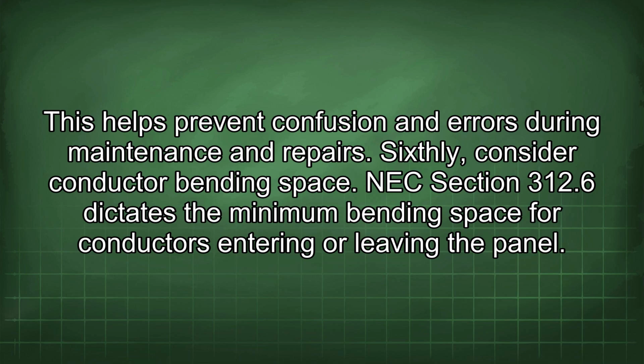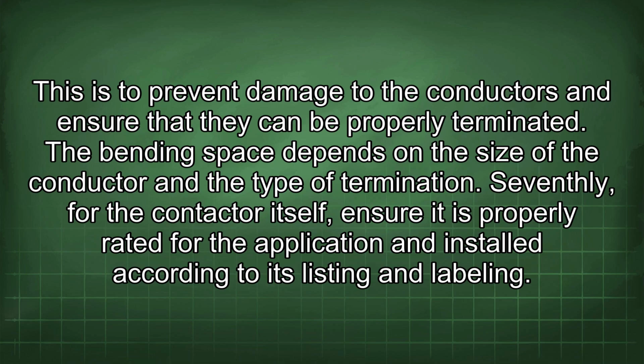Sixthly, consider conductor bending space. NEC Section 312.6 dictates the minimum bending space for conductors entering or leaving the panel. This is to prevent damage to the conductors and ensure that they can be properly terminated. The bending space depends on the size of the conductor and the type of termination.